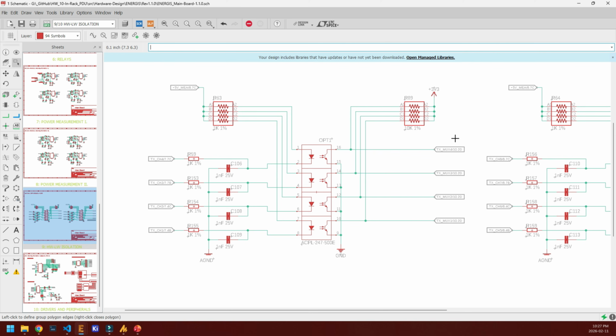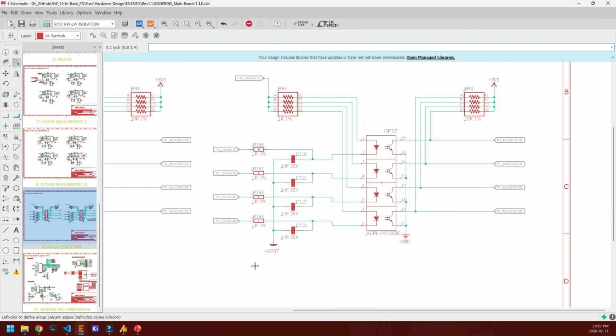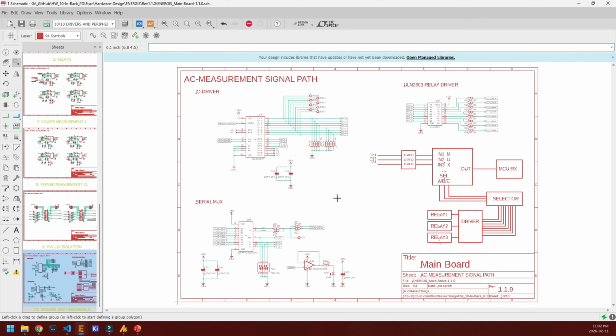The collectors are pulled to 3.3 volt by a 10K resistor. The emitters are tied to the digital ground. This makes each output an open collector style signal. When the opto is off, the 10K pull-up holds the line high, while when the opto is on, the phototransistor pulls the line low. When the transistor pulls low, the current is 3.3 volt divided by the 10K, which is about 0.33 milliamps. This is comfortably within what the optocoupler output can handle. The second opto is exactly the same, but it isolates the TX data for the channels 5, 6, 7 and 8. The next page ties together the relay control and the measurement signal routing.